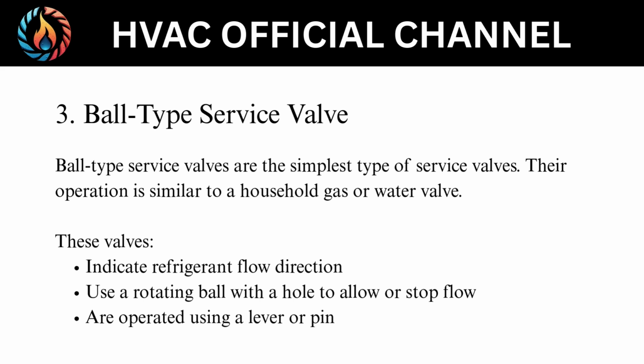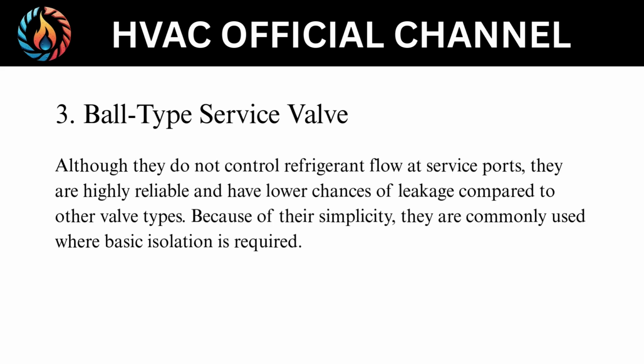3. Ball-type service valve. Ball-type service valves are the simplest type of service valves. Their operation is similar to a household gas or water valve. These valves indicate refrigerant flow direction, use a rotating ball with a hole to allow or stop flow, and are operated using a lever or pin. Although they do not control refrigerant flow at service ports, they are highly reliable and have lower chances of leakage compared to other valve types. Because of their simplicity, they are commonly used where basic isolation is required.